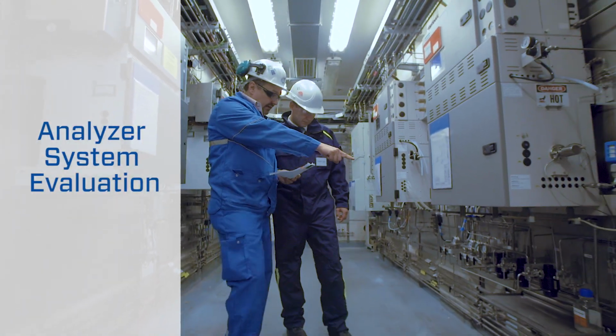Time delay is certainly the most common issue we see on the site, but we face also other problems like condensation, crystallization, filter clogging. At the end, we want to see the whole picture of the assembly and to check what are the root causes that lead to the problems.